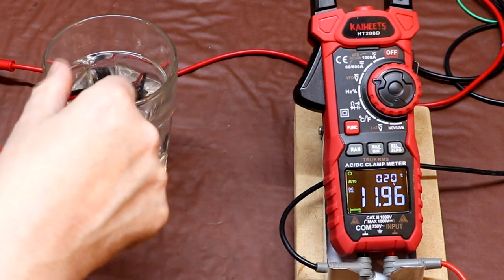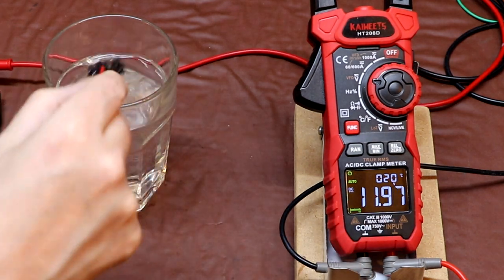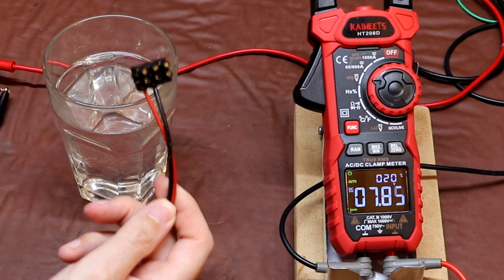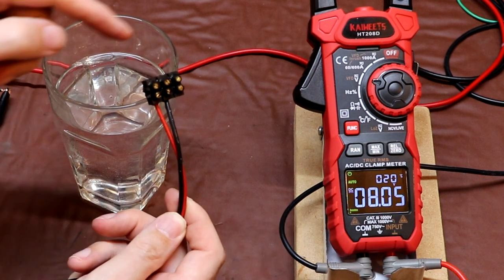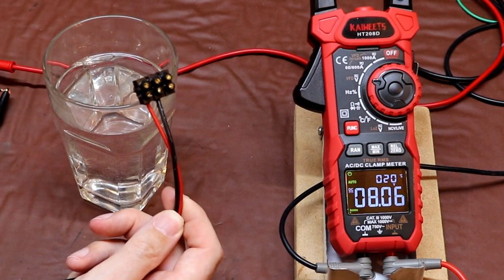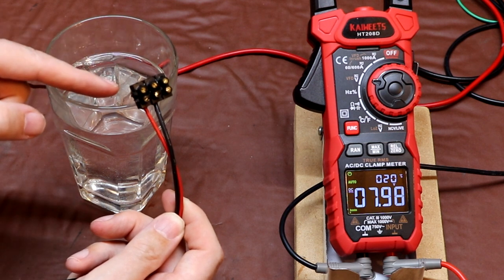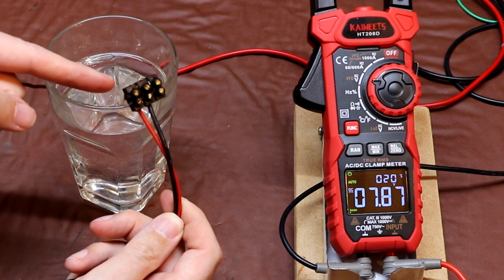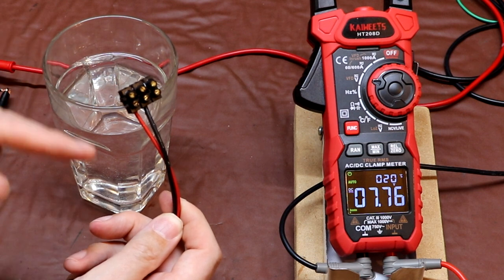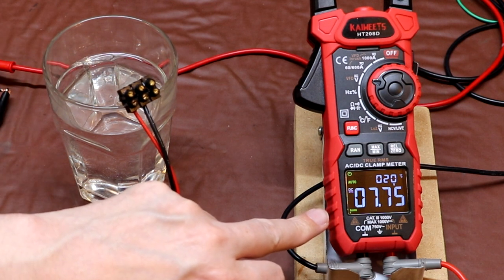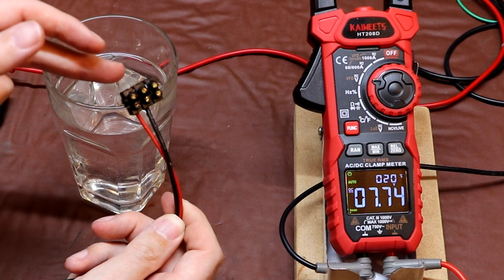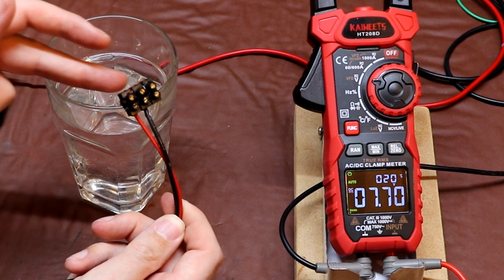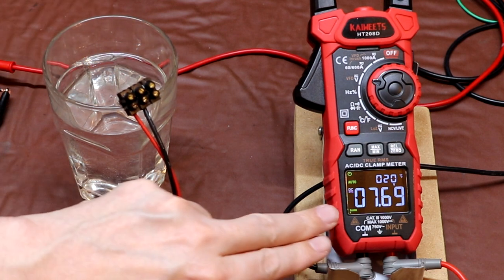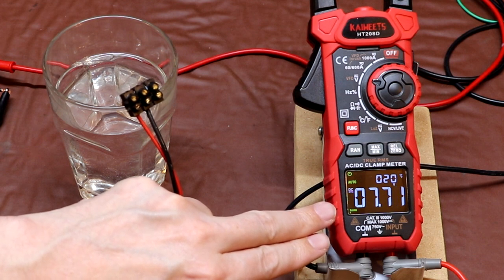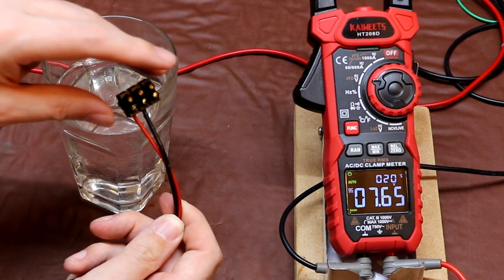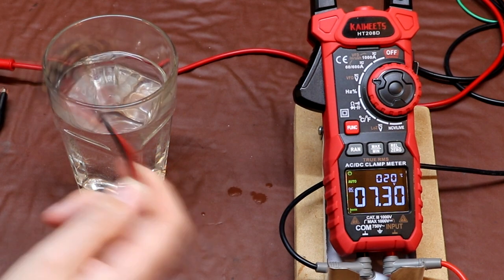So let's just take the connector block out of the water. And of course the actual voltage reading has dropped back a bit because we were getting a lot of conduction through the water itself, but we still have a conduction path here because the connector is wet. When this connector dries out totally, the reading will probably fall back to zero, but while it remains moist like this, we're going to be getting conduction through that moisture, which again is leading to this stray voltage or this phantom voltage being indicated on our cabling here.